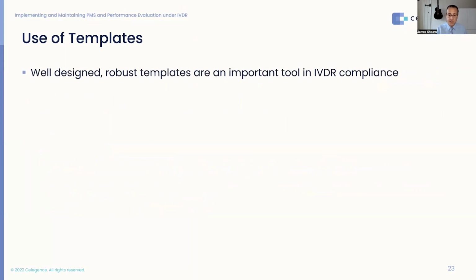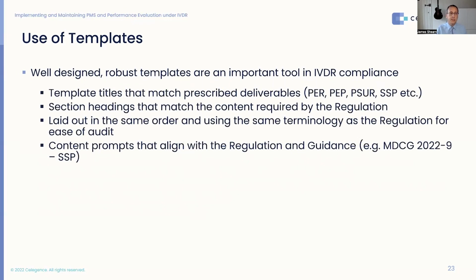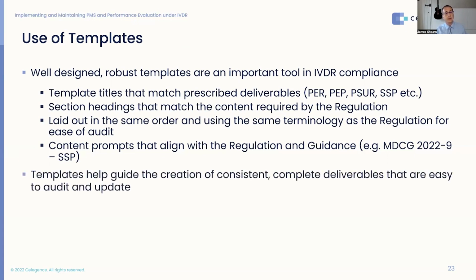Now, other things that can be very useful: use of templates. IVDR, particularly with respect to many of the deliverables we talked about today, is very prescriptive. So well-designed, robust templates are an important tool in IVDR compliance. When creating those templates, it's important that the template titles match the prescribed deliverables in IVDR: performance evaluation report, performance evaluation plan, summary of safety and performance, etc. Within those, the section headings should match the content required by the regulation and be laid out in the same order. When it comes to audit, an auditor can see this is what I'm required to have, and I can see I've got it because I've got the same title in the same order. Templates help guide the creation of consistent content and complete deliverables that are easy to audit and update.